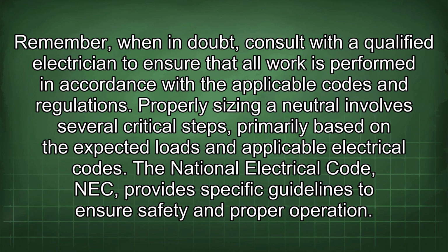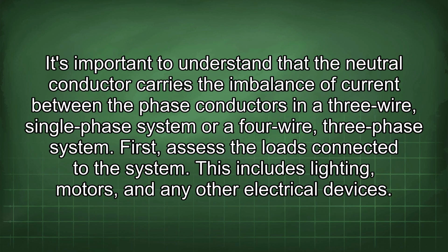electrical codes. The National Electrical Code, NEC, provides specific guidelines to ensure safety and proper operation. It's important to understand that the neutral conductor carries the imbalance of current between the phase conductors in a 3-wire, single-phase system or a 4-wire, 3-phase system. First, assess the loads connected to the system. This includes lighting, motors, and any other electrical devices.